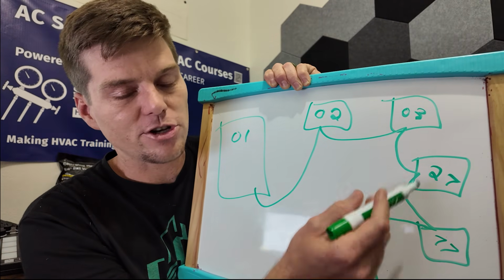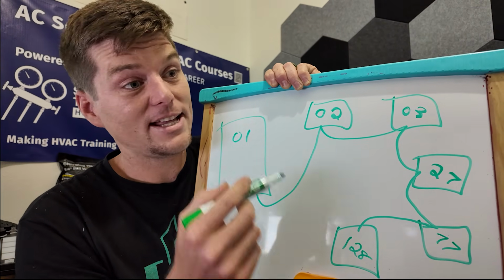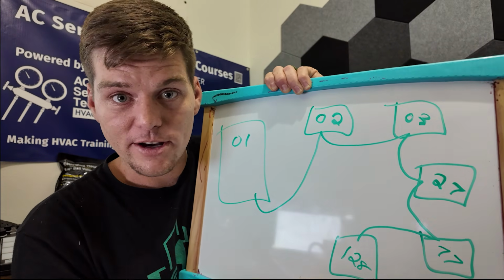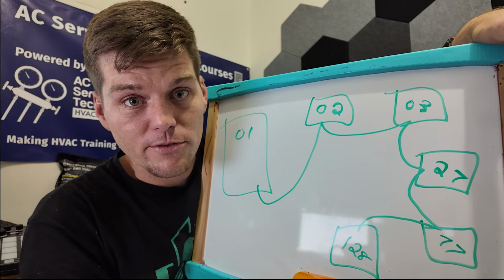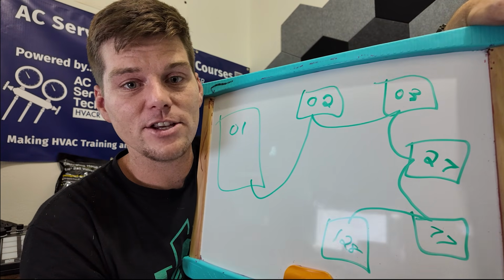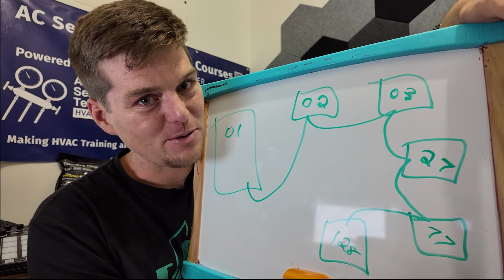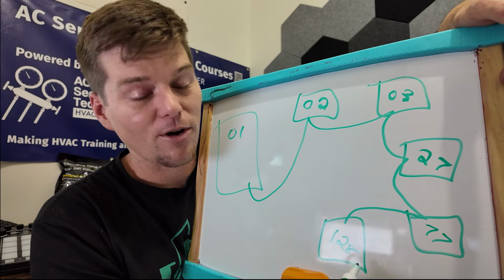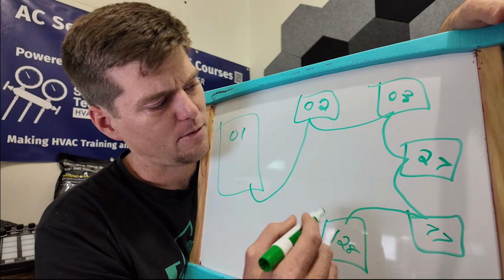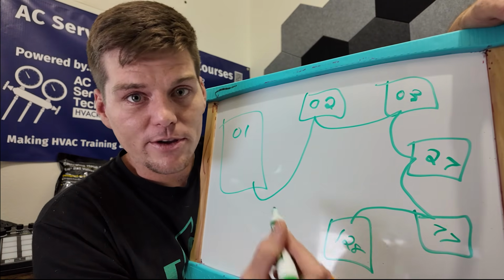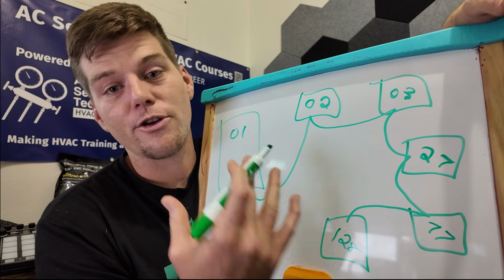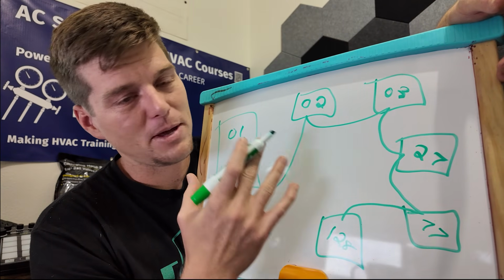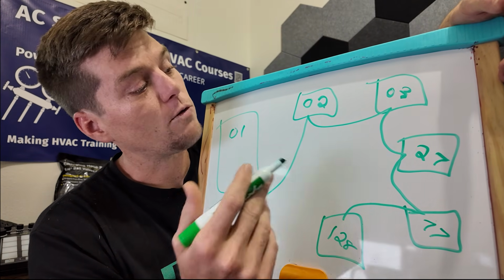If it doesn't see return signals back, or it gets back an irregular command from the indoor unit, it says, hey, what's going on downstream? If it gets 0 of the responses back that it sends to the indoor units, it generates a U4 error code, communication fault. Now, again, that can come back to a number of things. It could be a lack of power. It could be a break in the communication wire. It could be things that are hooked up in the network that aren't supposed to be, like float switches or thermostats on the F1, F2 in and outs, or other third-party devices. People get really crazy with this stuff, so don't overthink it.